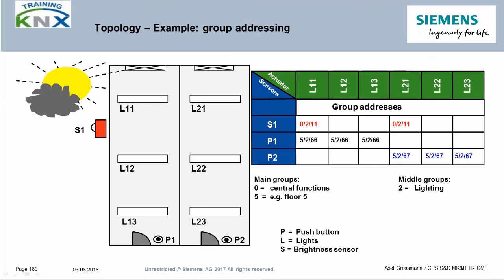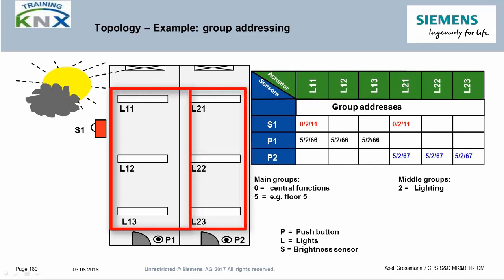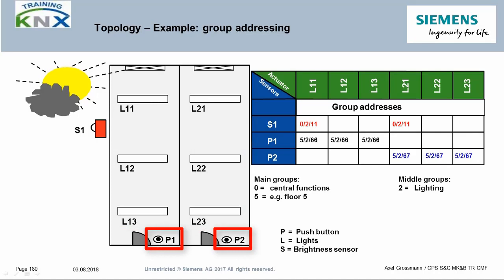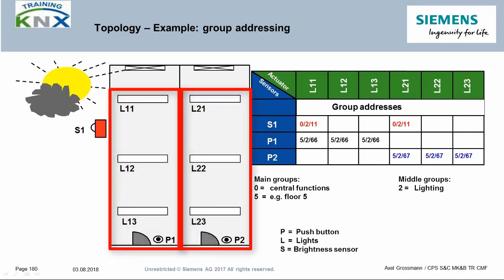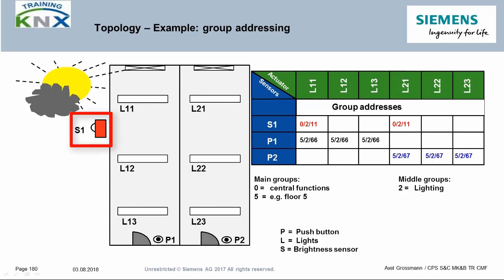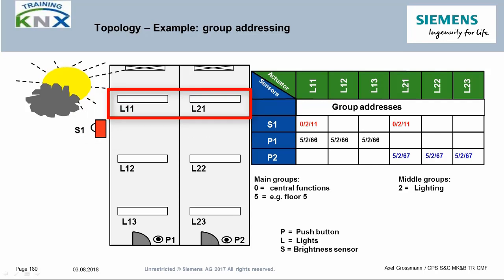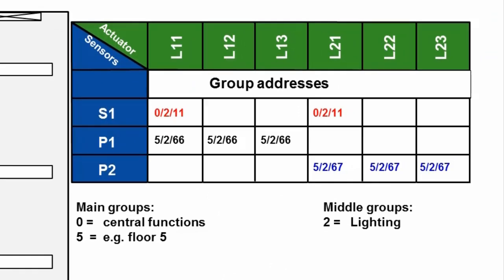Let's look at an example for the communication of group telegrams in different line constellations. The starting point is a small project with six switching actuator channels, three per room. The three channels of each room are switched manually and centrally via a single push button. A brightness sensor automatically switches off only the window lighting — lamps L11 and L21 — when it becomes brighter than a given threshold. The controlling group addresses for each function are listed in a table showing the sensor-actuator links.